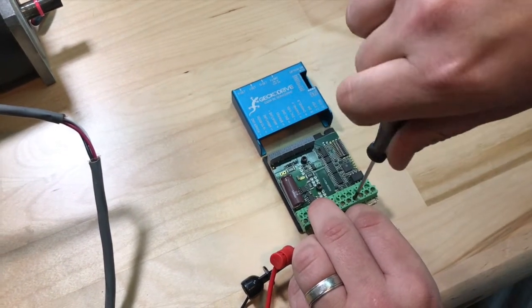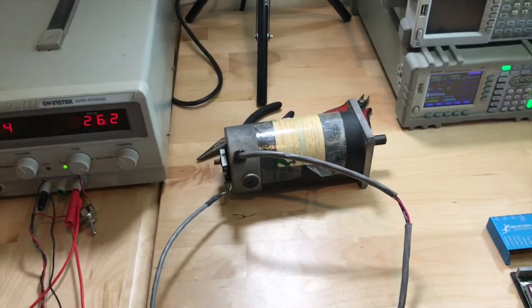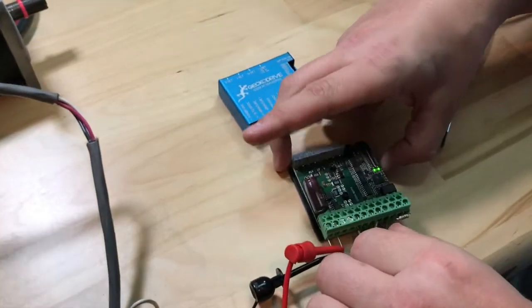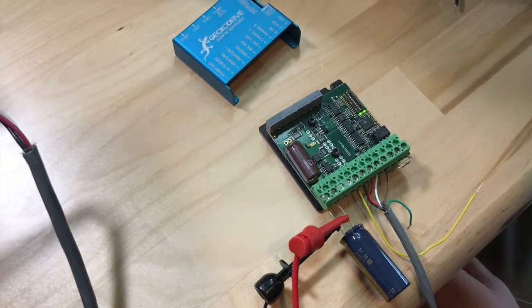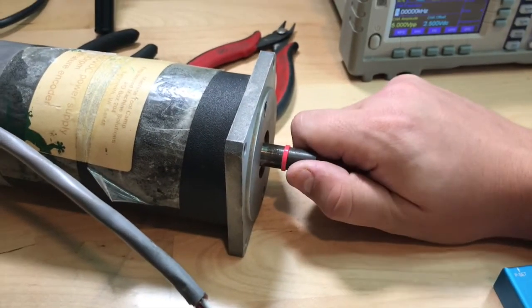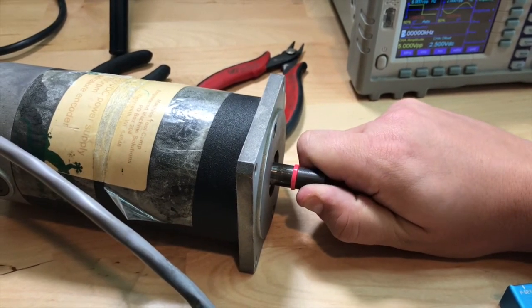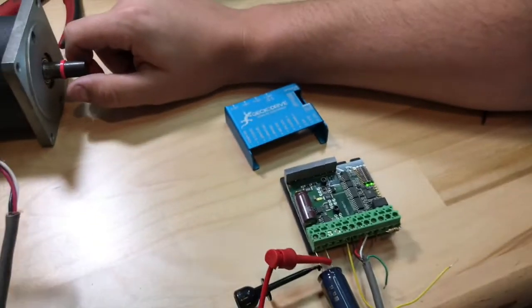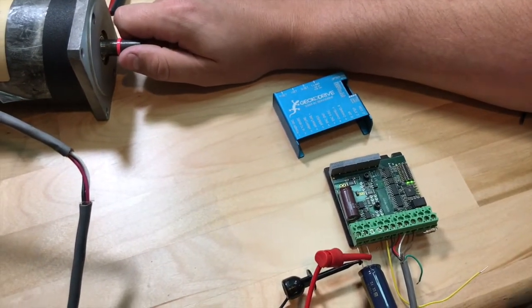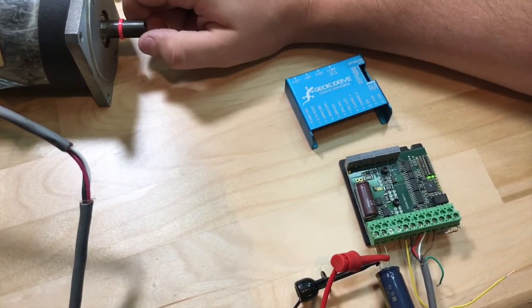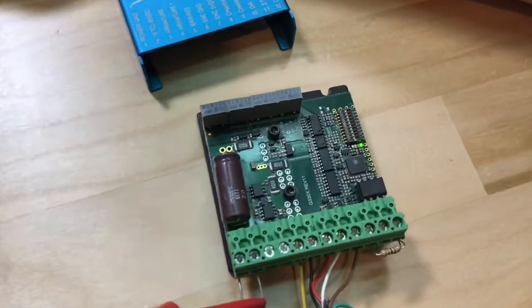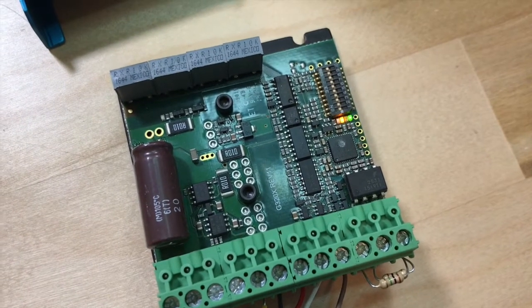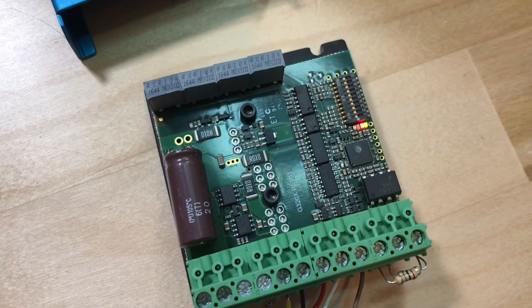Now what we'll do is turn power on and do the encoder test. We have the encoder connected, so I'm going to turn the motor shaft just to verify that we're getting feedback from the encoder. If you watch the drive while I turn the motor shaft, you'll see these LEDs change from in position, which is green, to warn, which is yellow, and then fault, which is red. It's beginning to fall behind and then it faults.